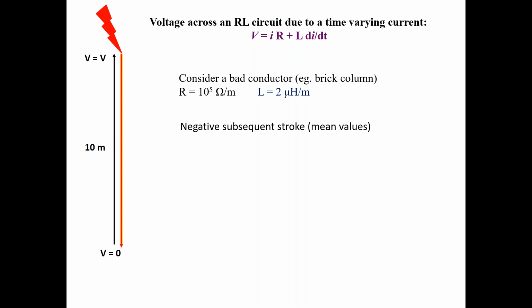And if I consider negative subsequent strokes, lightning has a first stroke and a subsequent stroke, both in negative lightning, then positive lightning. But usually negative lightning has quite high di/dt values, and negative subsequent strokes have the highest di/dt value. So if I take the mean values, the peak current is about 12 kiloamperes and di/dt is about 40 kiloamperes per microsecond at the peak. These values are from South African databases.